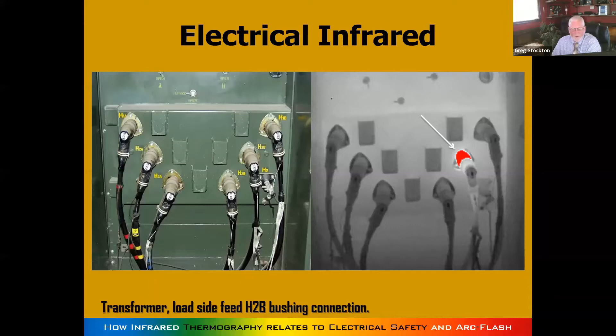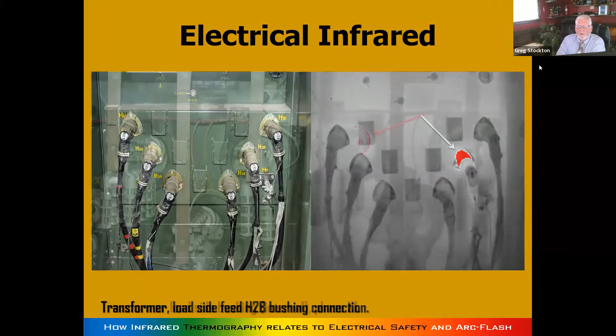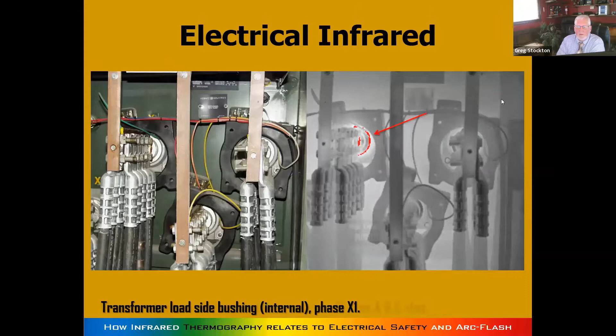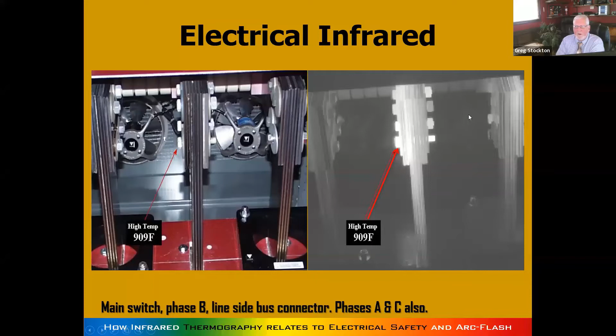Most of the time, the connections themselves fail because they either vibrate loose or corrode—there are lots of ways they can fail. They can also have mechanical problems, like these bushings not being tightened up. And there's always the case where, at the factory, it was Friday afternoon and they forgot to put the bolts on with the Belleville washers.